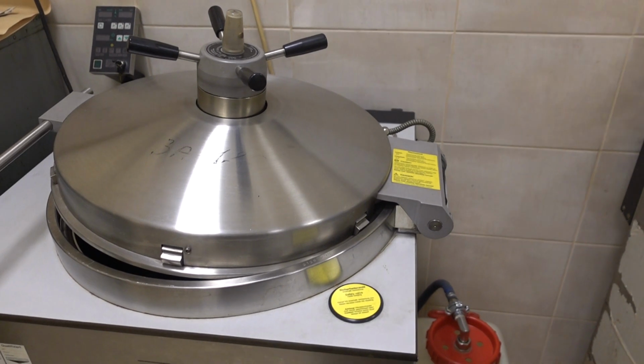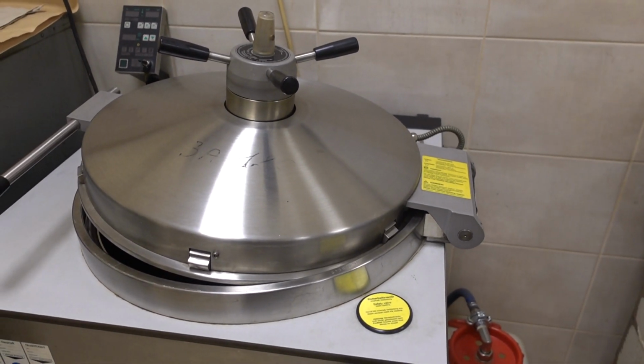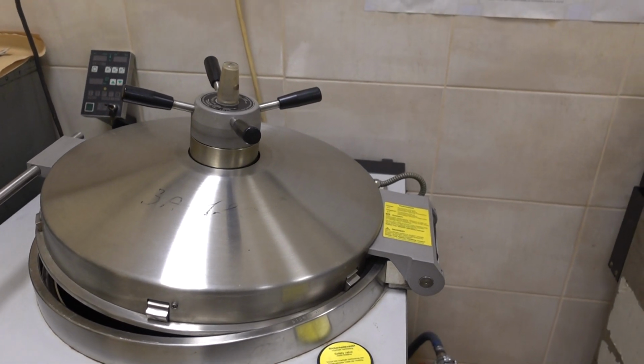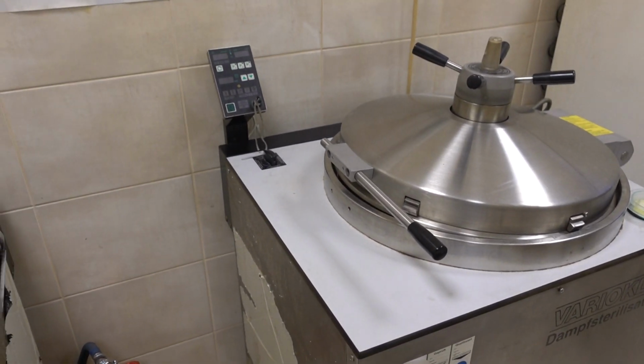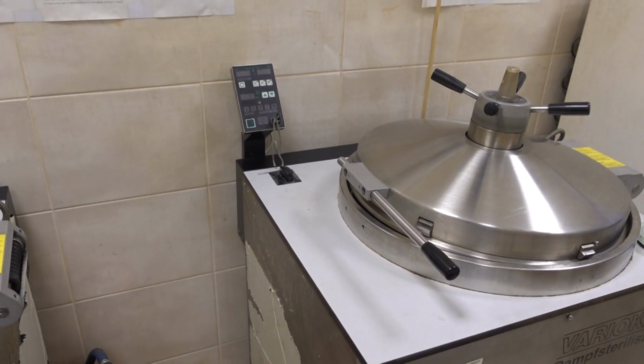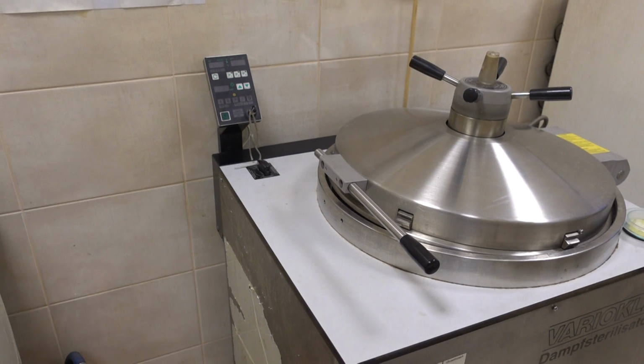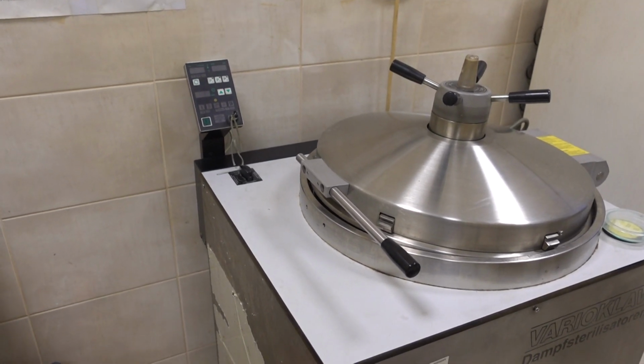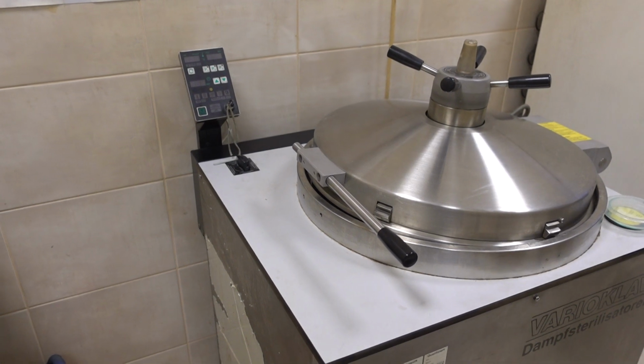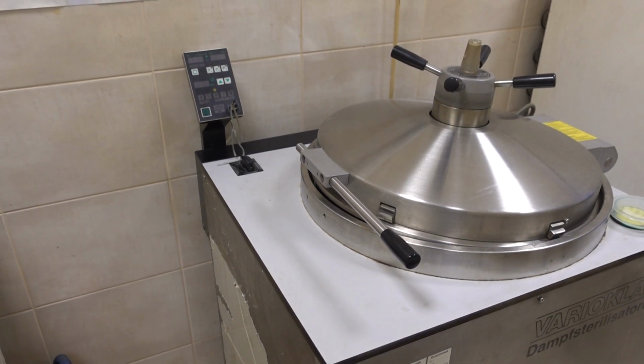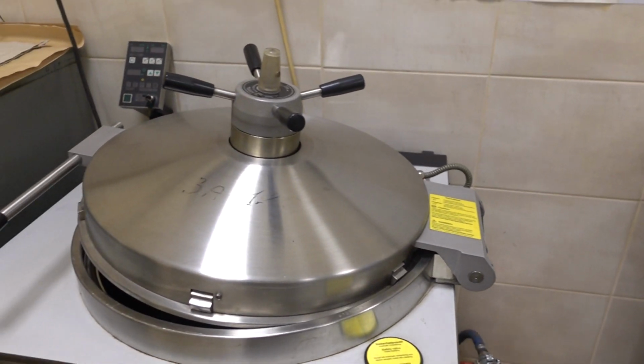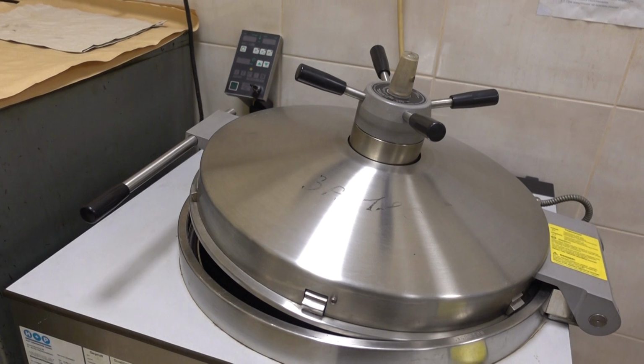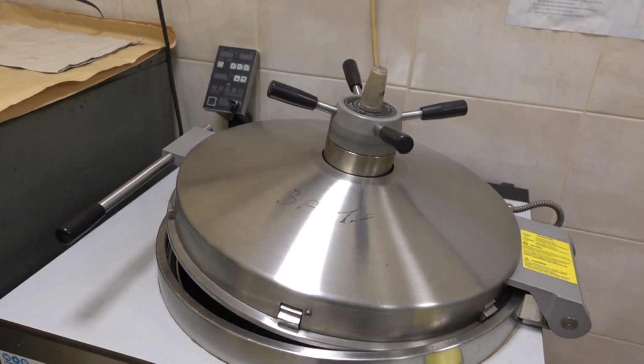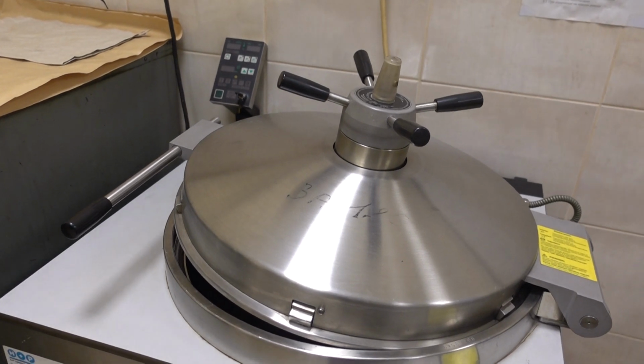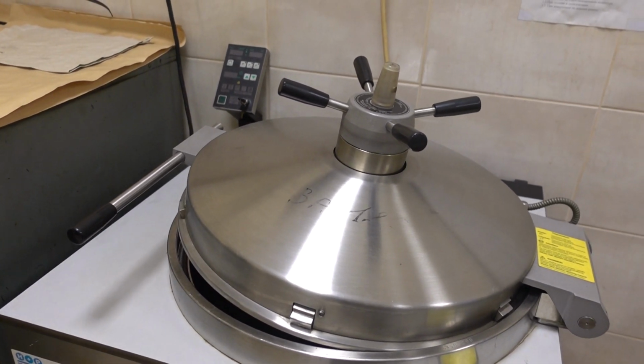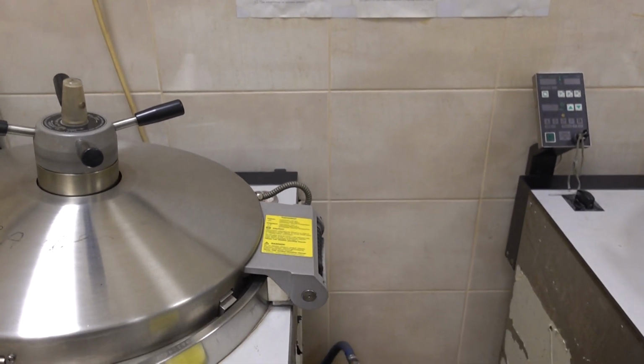Why do we have two autoclaves? Because one of them is figuratively clean and the other one is figuratively dirty. The clean autoclave, of course, it contains a lot of microorganisms, but we put there objects which we don't consider to be really contaminated with pathogenic infectious material. While the dirty autoclave, here we will sterilize only objects which we know per se that have been inoculated, that have been contaminated with really infectious material. And we should not mix the objects between two autoclaves.